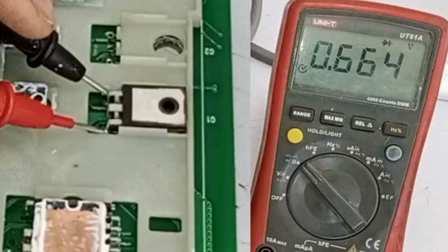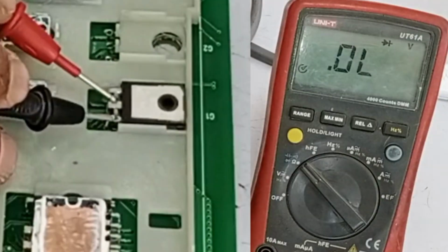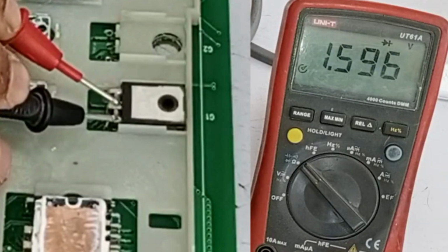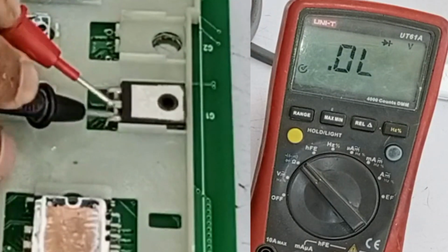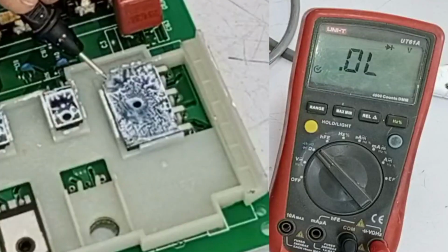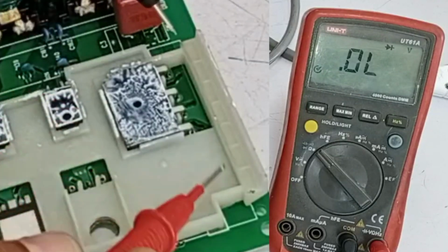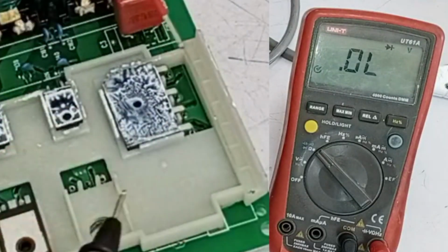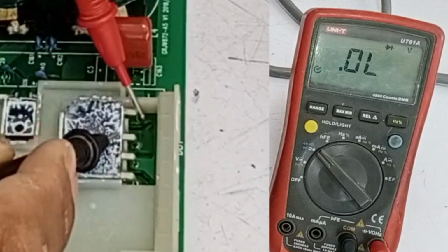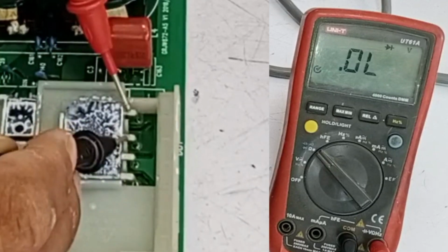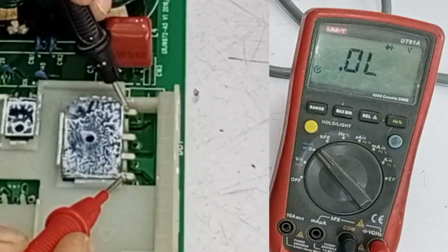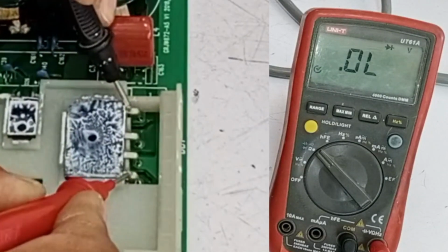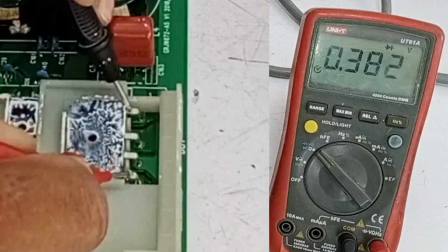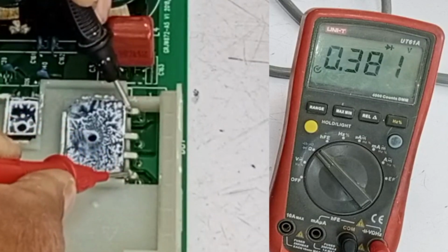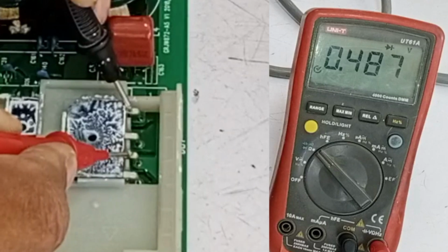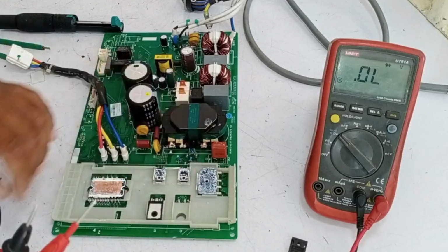Now I'm rechecking the IGBT and it's still showing the correct values, even when the polarity is reversed. There's no issue with the diodes either. They're all fine. Moving on to the rectifier, let's check its current status. I'll connect the positive side to the positive probe and the negative side to the negative probe. This shouldn't show any reading, as it's supposed to block the voltage in this direction. When I reverse the probes, placing the positive on the negative and the negative on the positive, it shows 0.831 voltage drop, which is correct. I checked other points, and they are also showing proper values, meaning everything else is in good condition.